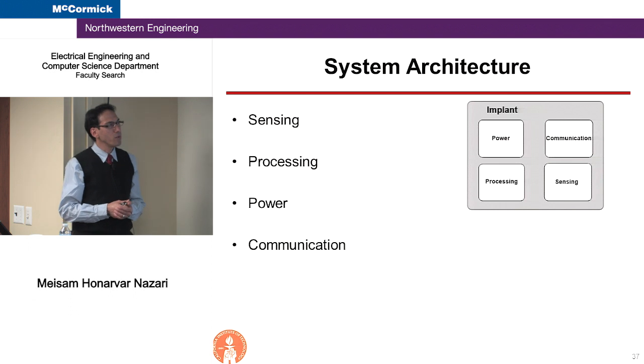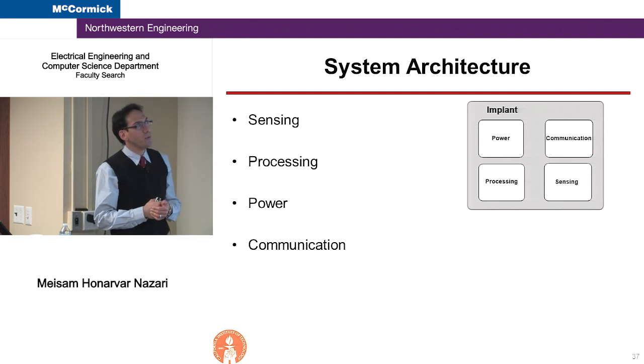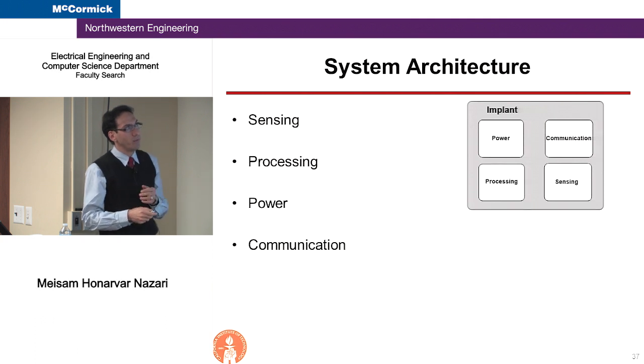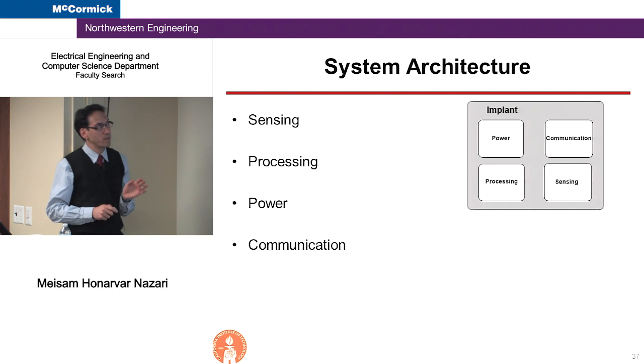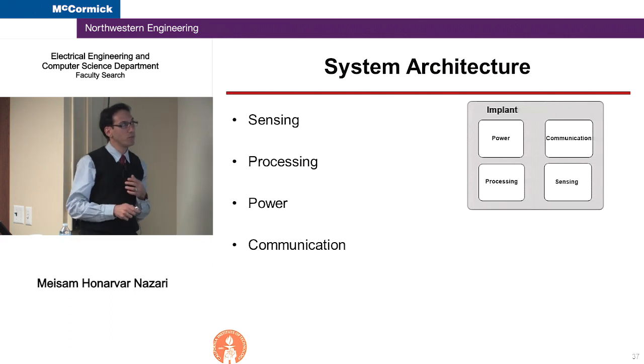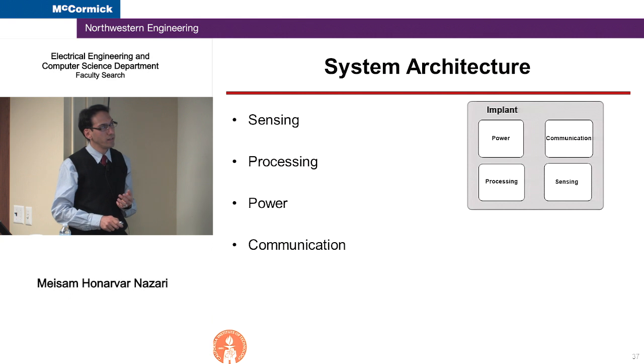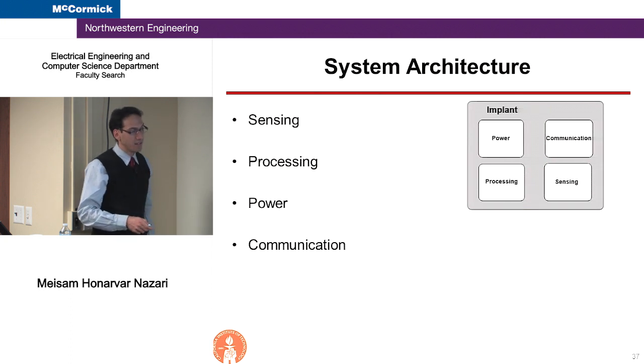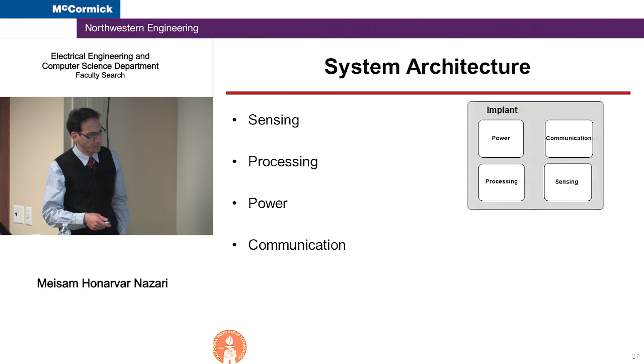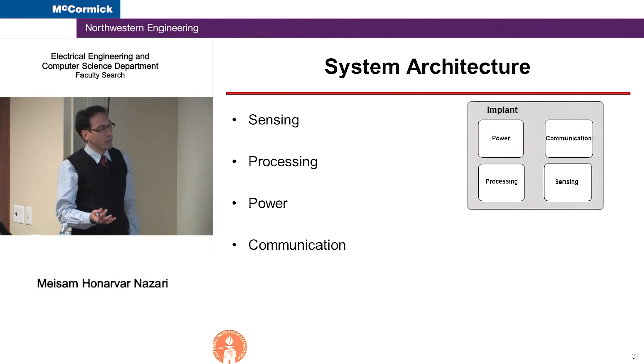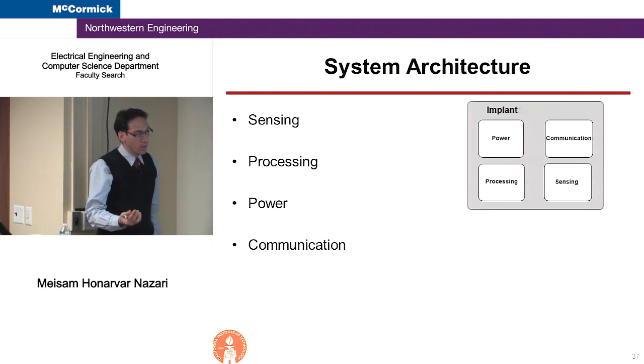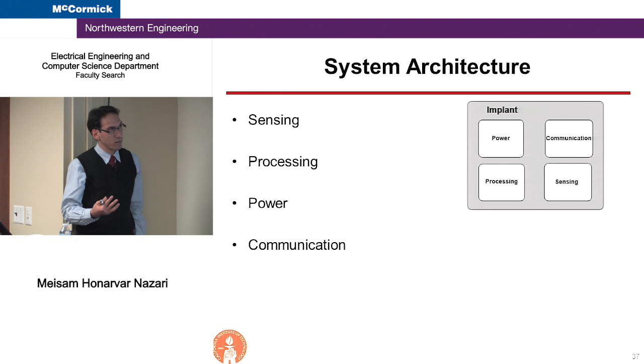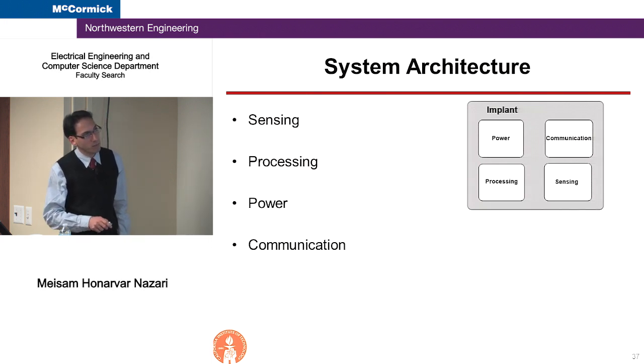So now, in order to do an implantable system that does glucose monitoring, we have to have a system that does first glucose sensing. This sensor will transduce the chemical signal into an electrical signal. This electrical signal needs to be processed. Also, we need to somehow power the device. And then lastly, but also very importantly, we need to do the communication with the outside world to inform the patient of their glucose level. So this is how an implantable continuous glucose monitoring system would look like.